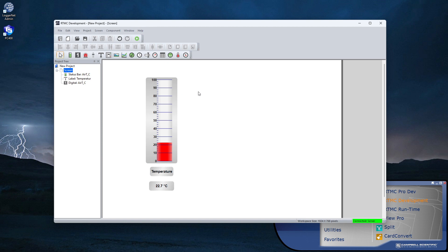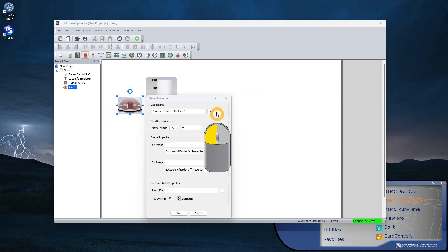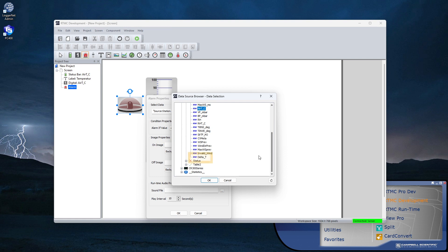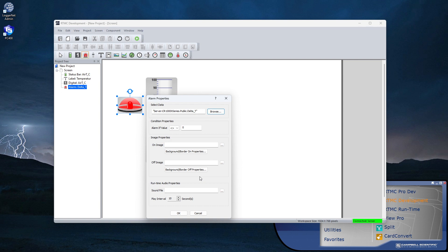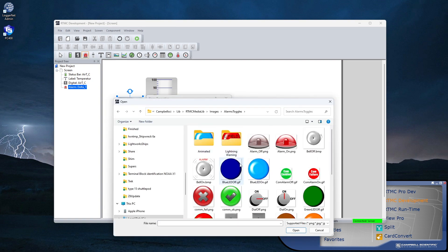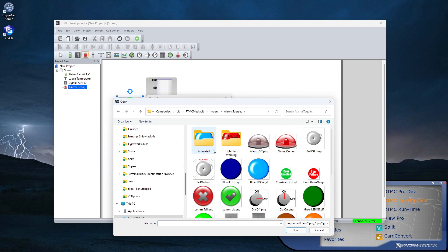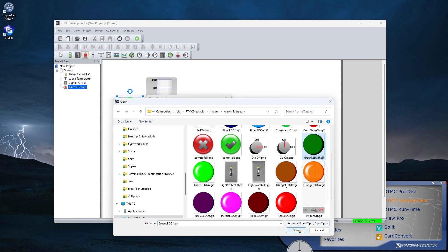Now I want to show some additional features. Alarms provide visual and/or audible notifications that a data value has exceeded a defined limit. In this case, I have a variable called Delta T that calculates the difference in temperature between the air and data logger. When the difference in temperature is greater than 3, I have an alarm condition. I can use any image I already have — many graphic file types are supported, and RTMC includes images as well. Select one image to be displayed when the condition is met, and another for when it is not.